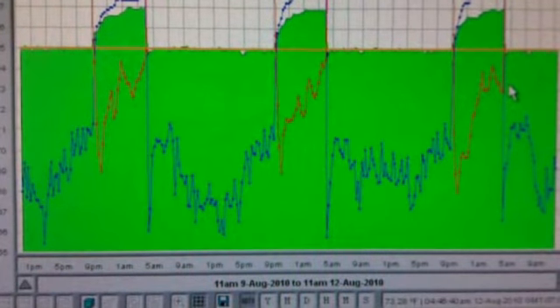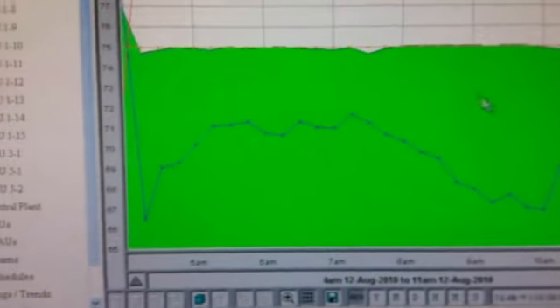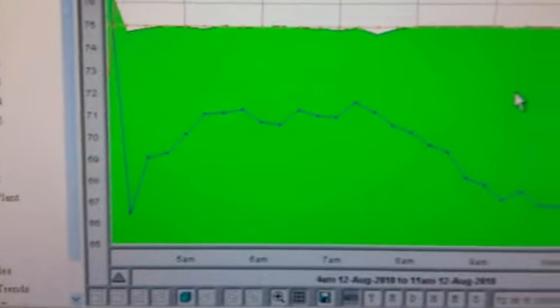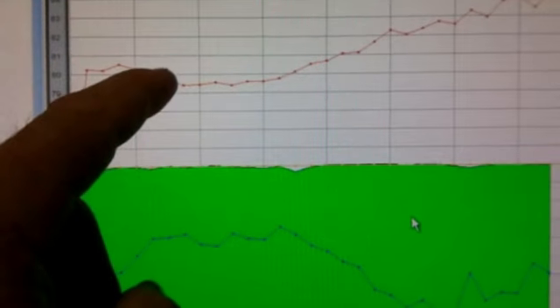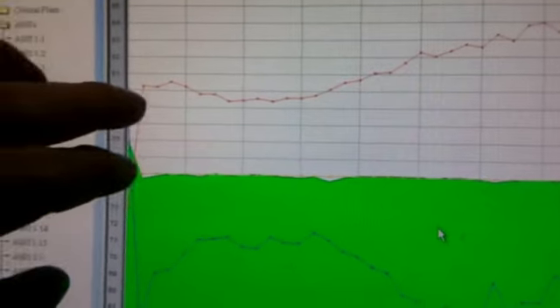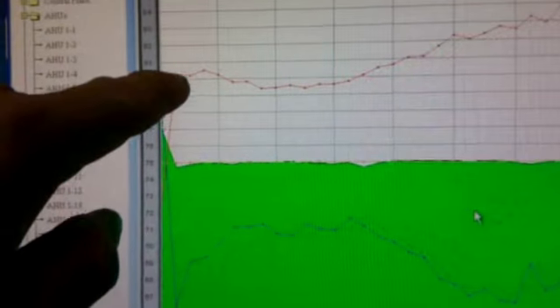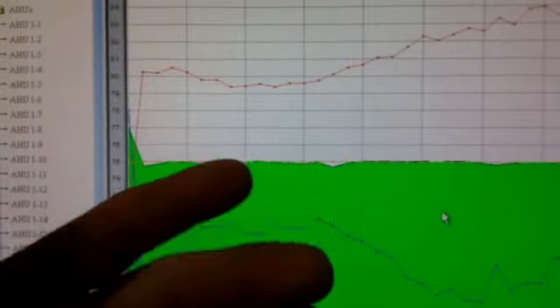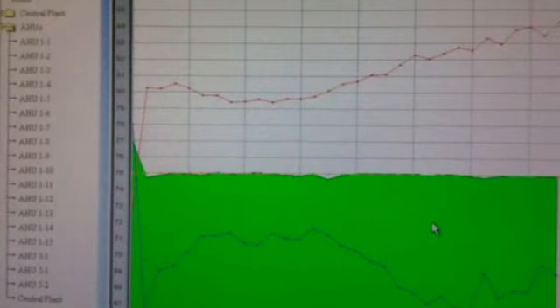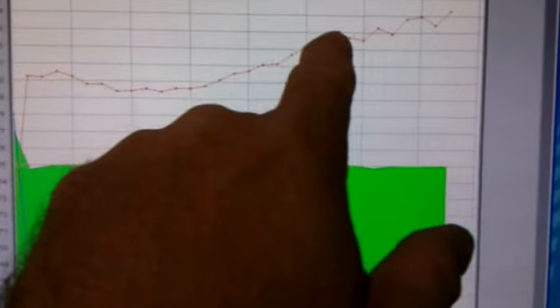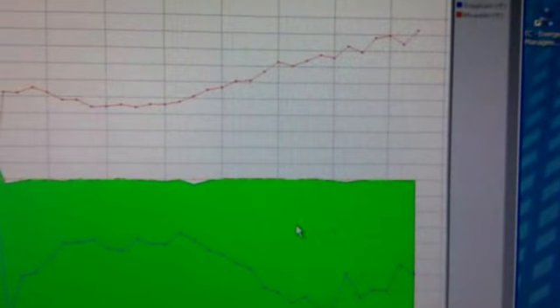Let's go looking for just today. Okay. Green is the space temperature. This is the mixed air temperature, which is affected by the outside air since it's bringing in some fresh air. So you'll notice that starting out in the early morning, 4 o'clock or so, it was just 82 mixed air, which is the 75 degree room temperature plus 80 something degree outside air. Now obviously it's about 106 outside, about 105 outside, so by now the mixed air is about 84.5 degrees.